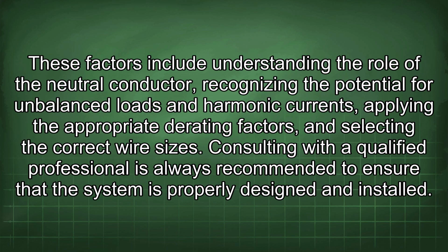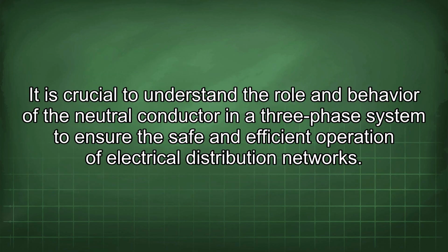These factors include understanding the role of the neutral conductor, recognizing the potential for unbalanced loads and harmonic currents, applying the appropriate derating factors, and selecting the correct wire sizes. Consulting with a qualified professional is always recommended to ensure that the system is properly designed and installed. It is crucial to understand the role and behavior of the neutral conductor in a three-phase system to ensure the safe and efficient operation of electrical distribution networks.